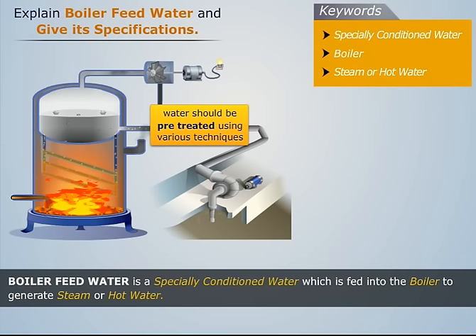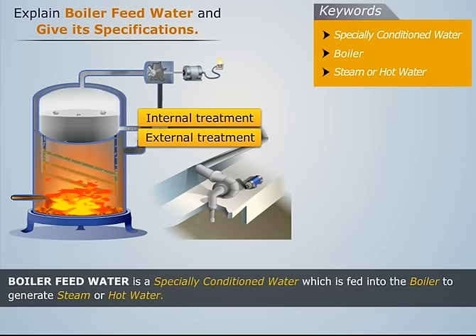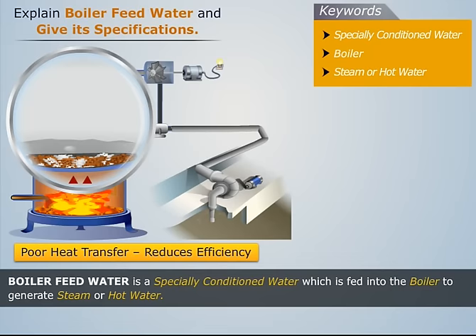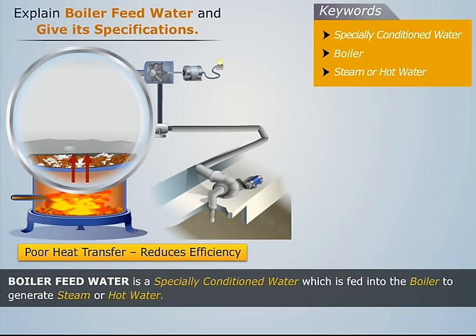In order to operate and maintain a boiler system efficiently, it is important to treat the boiler feed water properly. When steam is produced, the dissolved solids become concentrated and form deposits inside the boiler, leading to poor heat transfer and reduced efficiency. Also, dissolved gases such as oxygen and carbon dioxide react with the metals in the boiler system, and this leads to boiler corrosion.